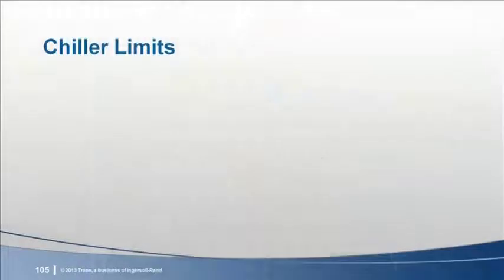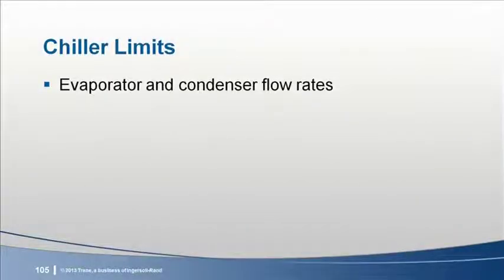Now, let's look next at the chiller. The first limits are easy: minimum and maximum condenser and evaporator water flow rates. The minima are to ensure good heat transfer and controllability. The maxima avoid tube erosion and vibration issues.